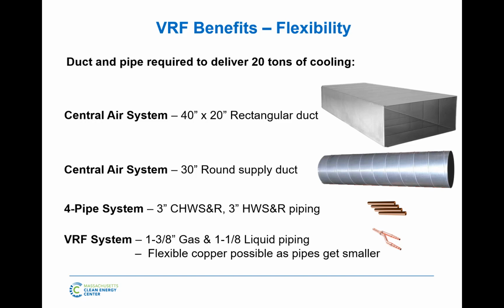Well, you're looking at insulation. The pipe itself is usually 1 inch, 1 3/4 inch, 1.5 inches, maybe the largest you'll see, and they go as small as 1/4 inch. So even if you see a pipe that's 1 inch, it's probably got a 1/2 inch copper in there, and it's got a 1/2 inch wall insulation. So the size of these units makes VRF very prominent for a retrofit.